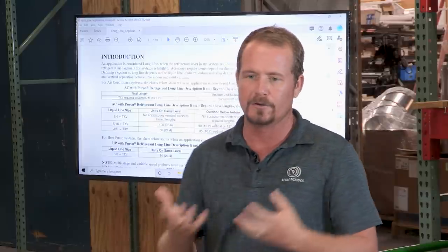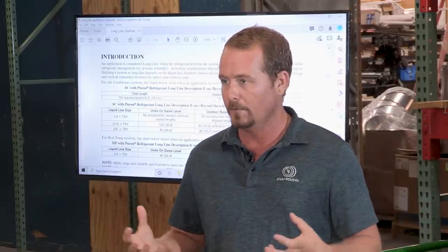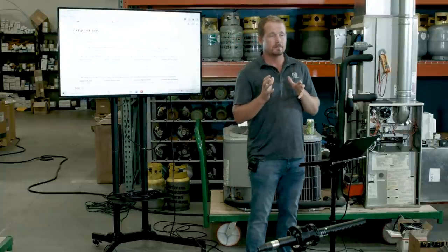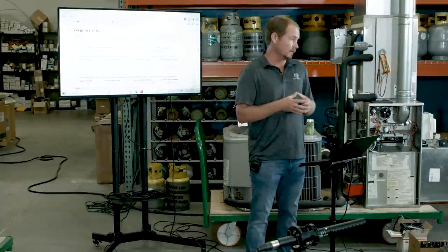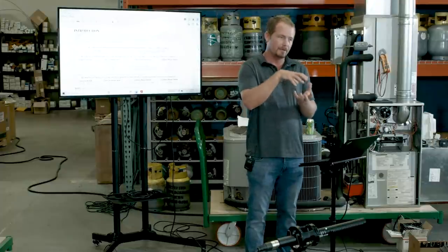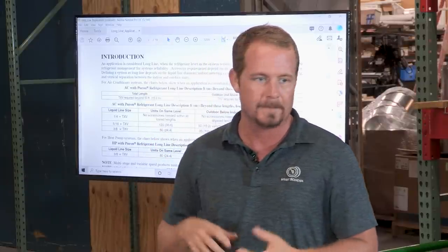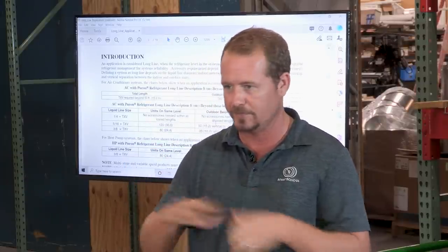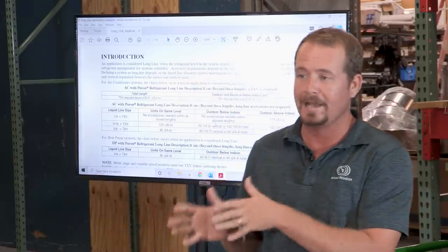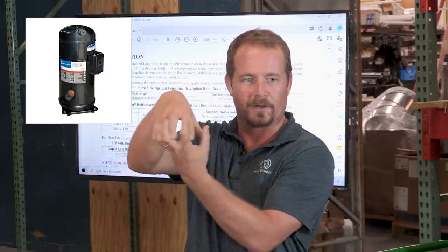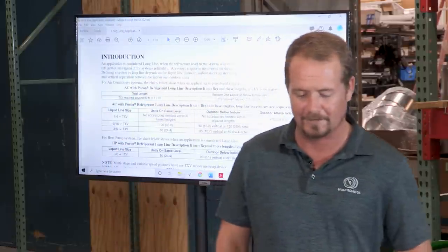We definitely can't get liquid refrigerant into the head of the compressor, the actual compression chamber, depending on the type of compressor it is. We don't want to get it in where it's actually doing compression. Although, with certain scroll compressors, they can actually even deal with a little bit of liquid refrigerant all the way through the head because of that ability to move and flex. If it didn't have that axial and radial compliance that a scroll has, if you put wet gas into it and it tried to compress it, it would just immediately destroy the compressor. Now, wet gas is going to destroy the compressor either way. Liquid refrigerant entering the compressor is going to destroy it one way or another. It just will be a slow death if you have some ability to handle it. When I'm doing this, I'm doing a scroll. This is a scroll compressor, by the way. In case you couldn't tell.